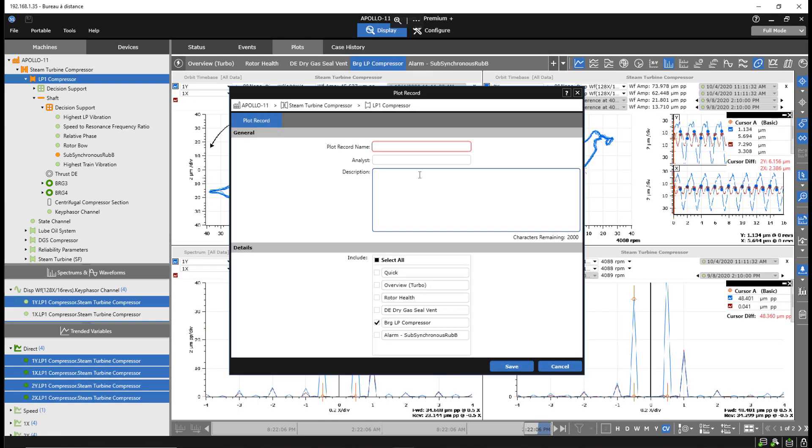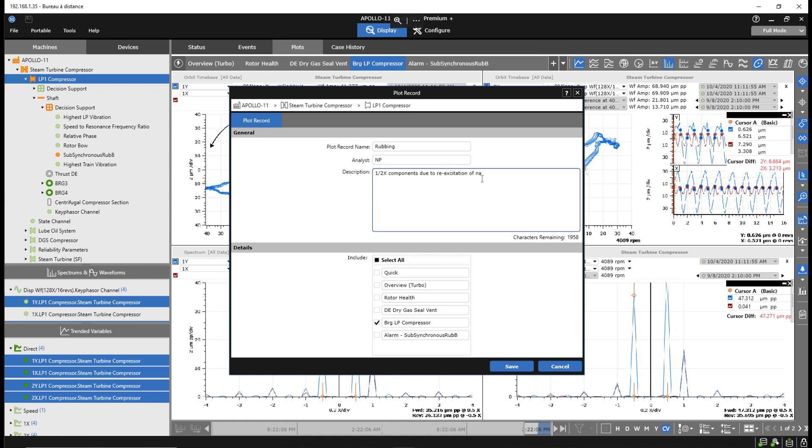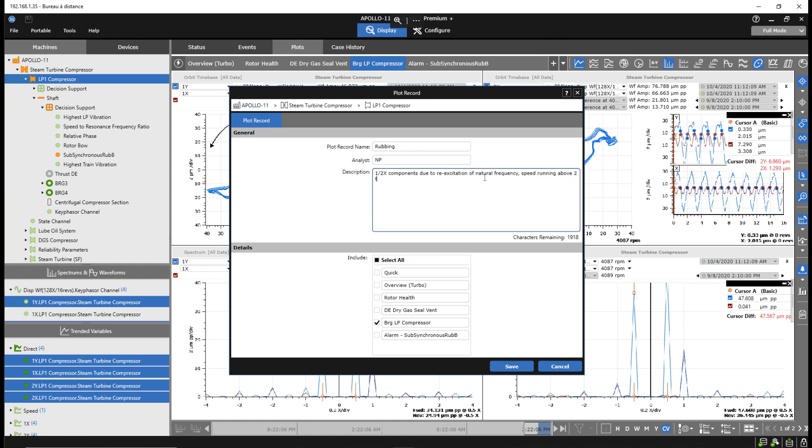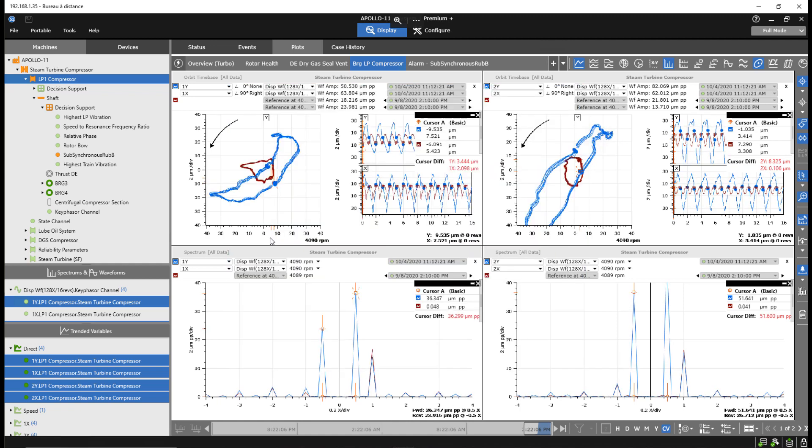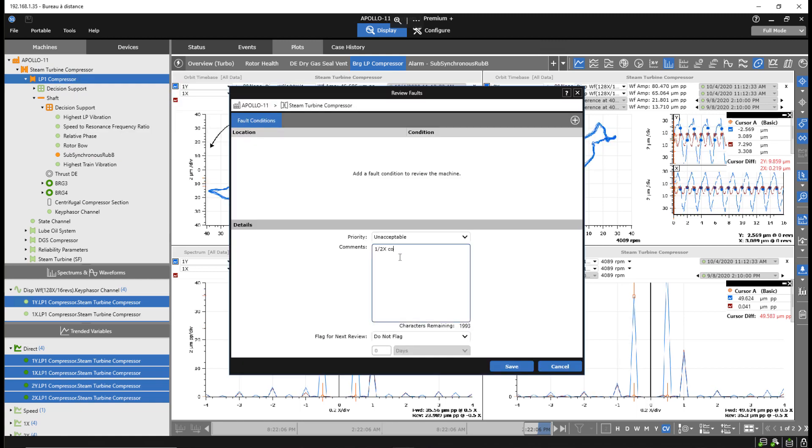The engineer then documents the rub condition in System One along with supporting details. The engineer instructs operations to achieve a stable thermal condition which then eliminates the rub condition.